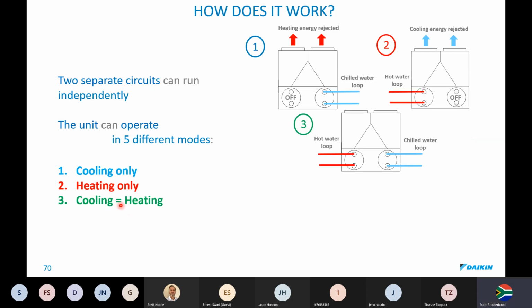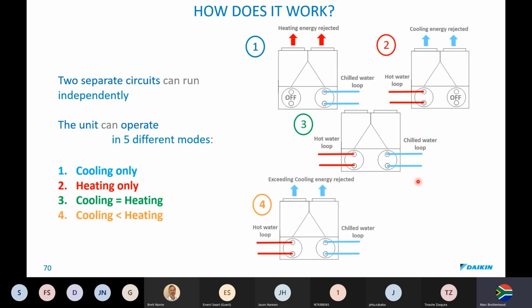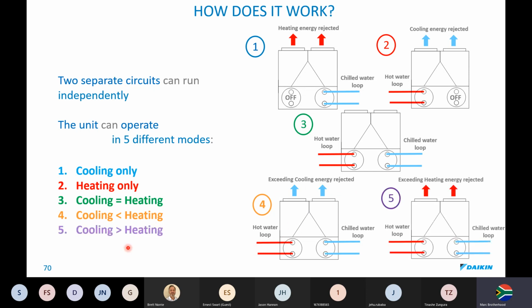Here we can have cooling, equal cooling and equal heating operation. Here, if the cooling is less than the heating, the chiller says, what do I do? What is this coil? Does it become an evaporator? Does it become a condenser? It makes a judgment. So it can still provide you hot and cold water regardless of the ambient temperature. Or if your cooling demand is more than your heating demand, say in a hospital, then we're going to switch functionality on these units. Notice though that these shell and tube heat exchangers are still dedicated. Heating will always be on this side, cooling on this side. These are never going to change around. But the technology is going to allow your coils outside to become either an evaporator or a condenser. So these are the 5 different options that this chiller can run in.